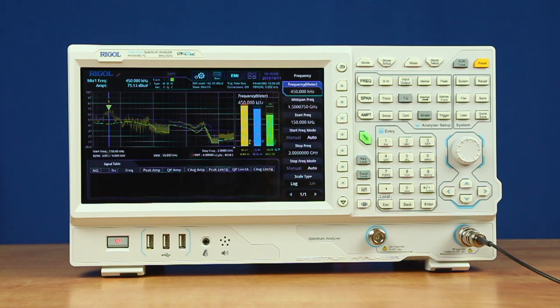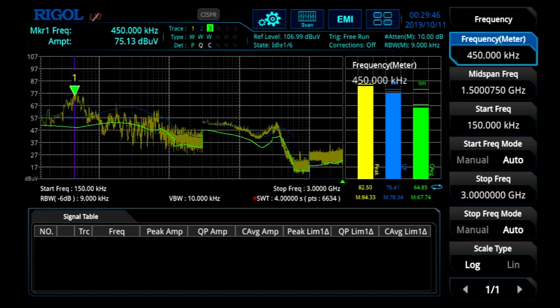Rigol's embedded EMI mode in our real-time spectrum analyzers is now available at an incredible value for engineers doing radiated, conducted, and immunity testing below 3 GHz. Switch the instrument to the optional EMI mode to test versus established limit lines, identify and retest peaks, and debug with our live monitor using multiple detectors simultaneously.